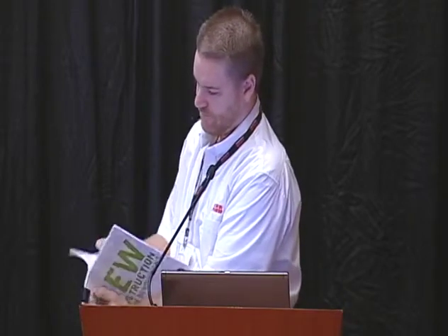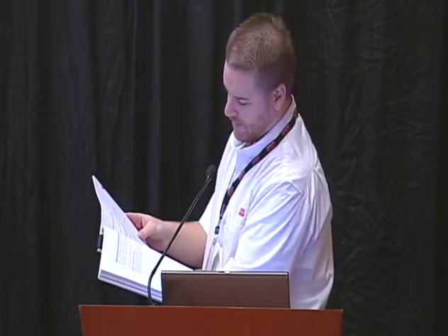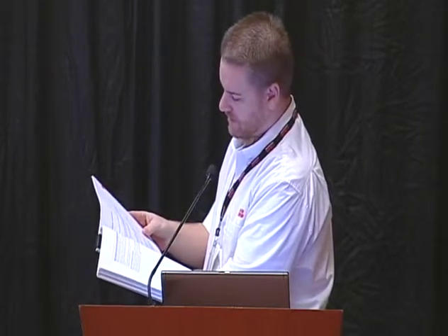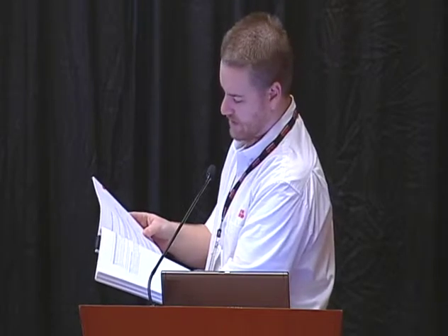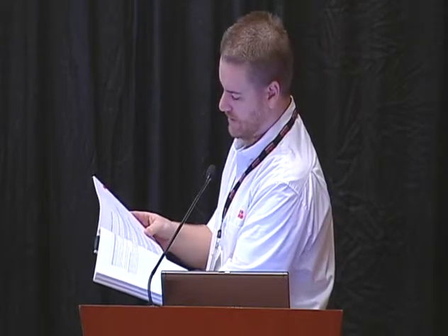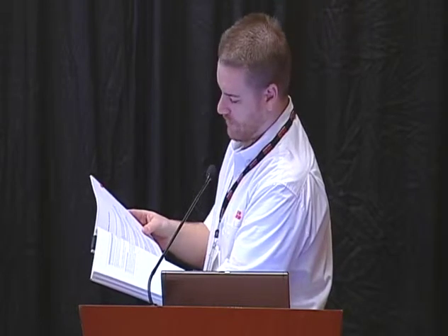So if you go ahead and read through LEED here, basically, develop a plan to evaluate building and energy system performance, characterize the building and energy systems through energy simulation or engineering analysis, install the necessary metering equipment to measure energy use. Install the necessary metering equipment. So as soon as people read that, they think, well, I need to go out and install a whole bunch of meters. What did I say earlier? VFDs can measure kilowatt hours.